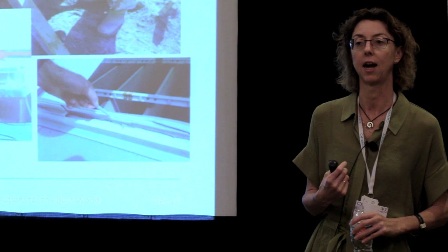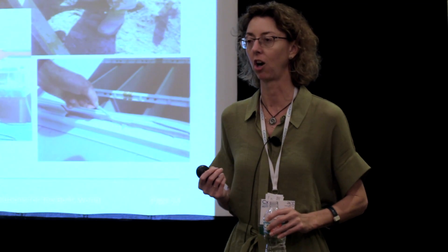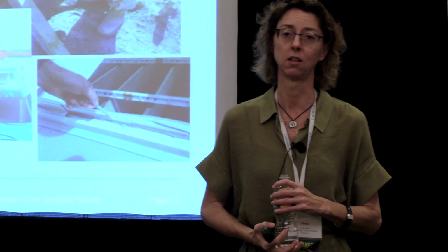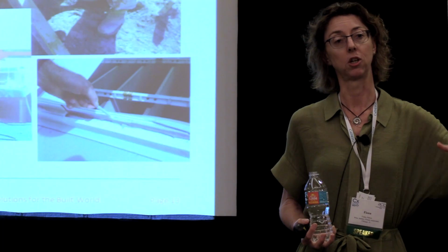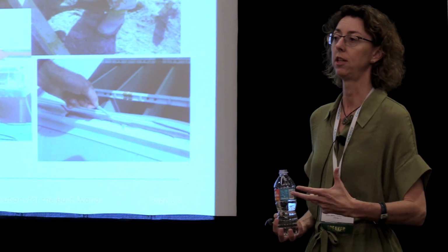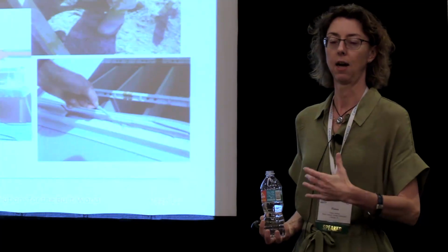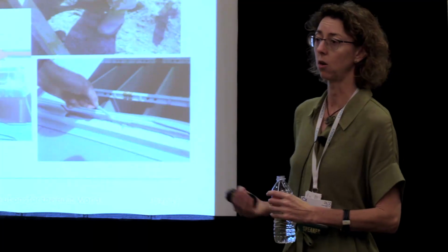I've spent numerous days, unfortunately, with a testing agent under my contract, having them arrive on the job site and say, well, I'm here, you've got to pay me for that day regardless of whether I pull my certified calibrated nozzle out or not, and pay me $3,000. Only to find I can't get my test agent onto the side of the building like I need him to be because they're doing safety training or they've had some other problem. They don't have hoses long enough, or we don't have the right water pressure to the job site. So all of these are challenges that come along with testing that ideally you want to put back onto the contractor, to ensure that they really do meet all the objectives of being able to perform the test.